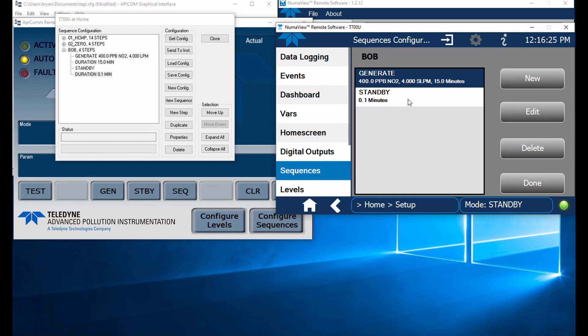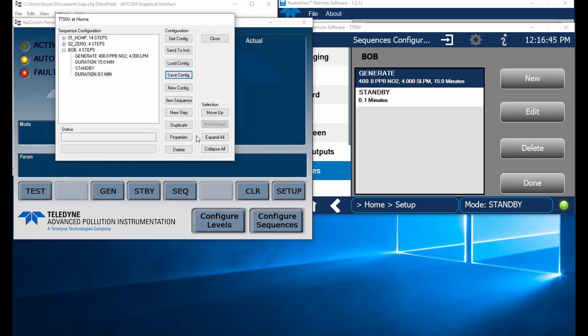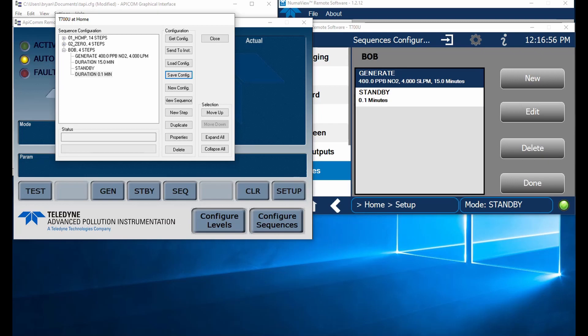So there you go. This is our workaround for transferring sequences. Now I can take this sequence and save it. I can then send it to another instrument. If I've got it stored as a file here, you can save that config to the hard drive. Now when I connect to my other T700 at another station or on the bench here, I can send this same sequence on through all of those machines. Works really well. It's a little easier to edit it. But hopefully that will solve a lot of problems for you guys that are trying to do this exact thing. Thanks a lot. Have a great day.